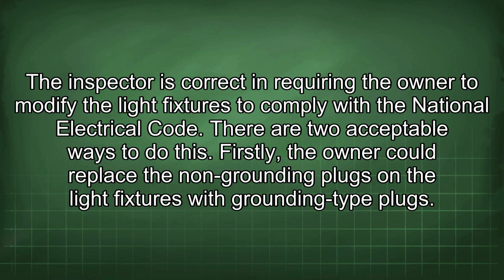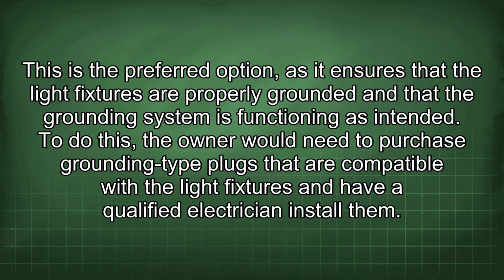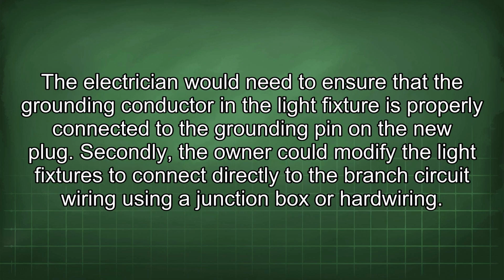There are two acceptable ways to do this. Firstly, the owner could replace the non-grounding plugs on the light fixtures with grounding-type plugs. This is a preferred option, as it ensures that the light fixtures are properly grounded and that the grounding system is functioning as intended. To do this, the owner would need to purchase grounding-type plugs that are compatible with the light fixtures and have a qualified electrician install them. The electrician would need to ensure that the grounding conductor in the light fixture is properly connected to the grounding pin on the new plug.